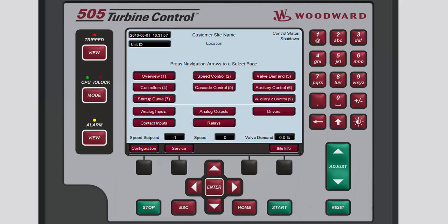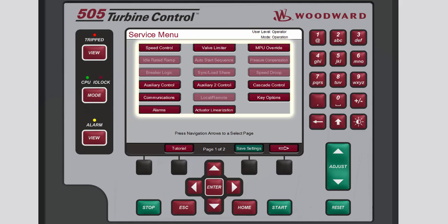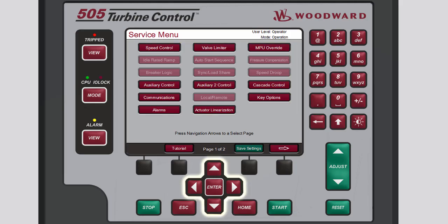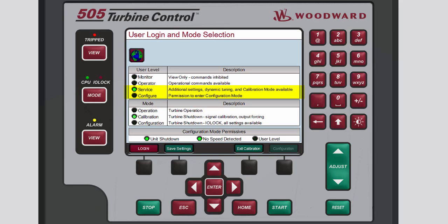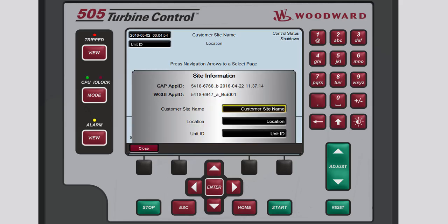To open the Service Menu from the Home screen, press the black Function key below Service. The Service Menu contains navigation buttons to all the service-related parameters and special features of the control. To select any of these buttons, use the navigation crosskeys to highlight the applicable button, then press Enter. To make changes from the Service Menu, you must be logged in at either the Service or Configure User Level and the unit must be placed in either Calibration or Configuration Mode.